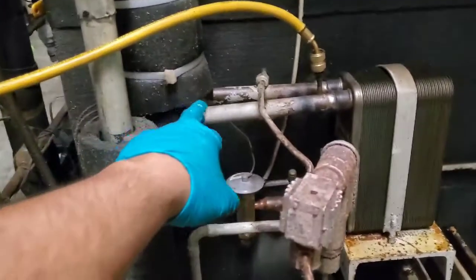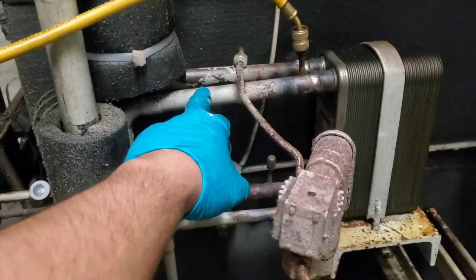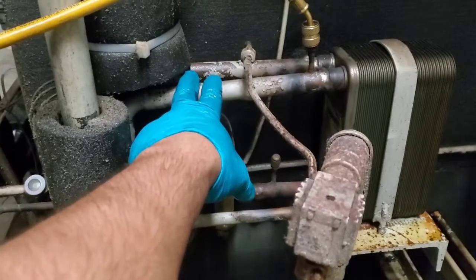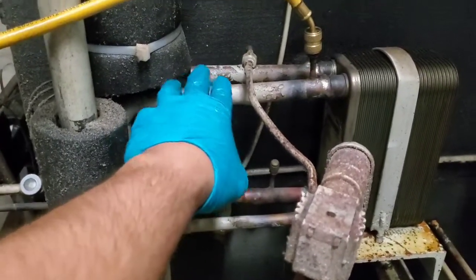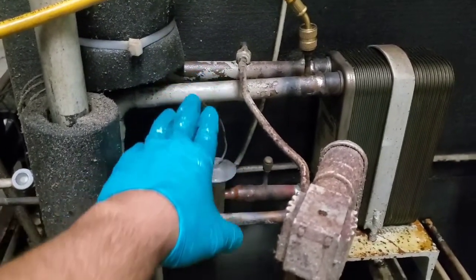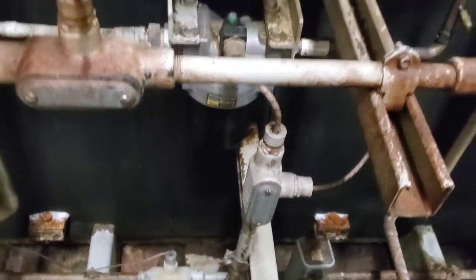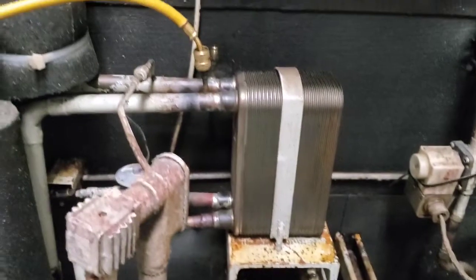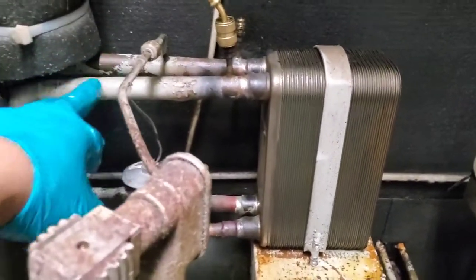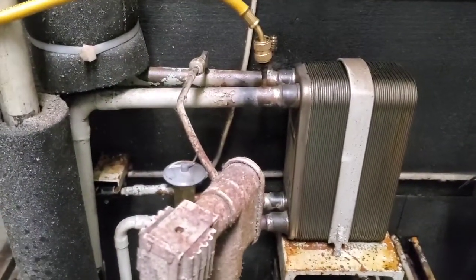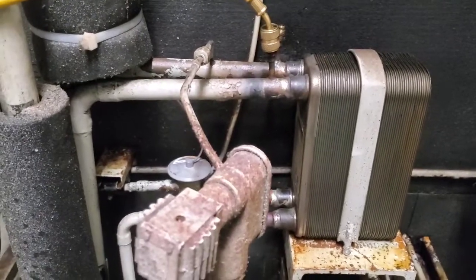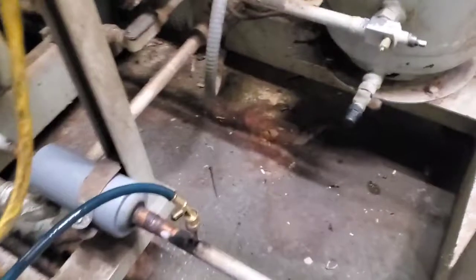So now that we've gotten all the oil out of the system, it's now under about 200 something PSI of vapor. We've got to get that vapor refrigerant out so that we can open up the system down here at the oil canister and change that filter. So now we're going to recover this refrigerant out of this section by isolating with isolation valves that are already in place, and we're going to put it back into the same circuit here in the liquid line.